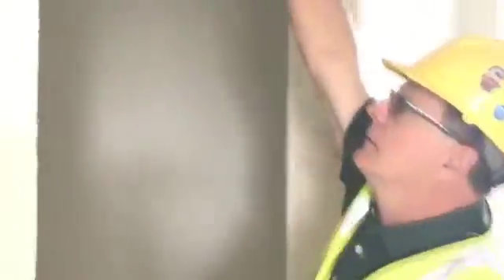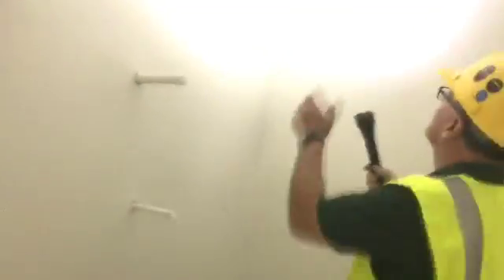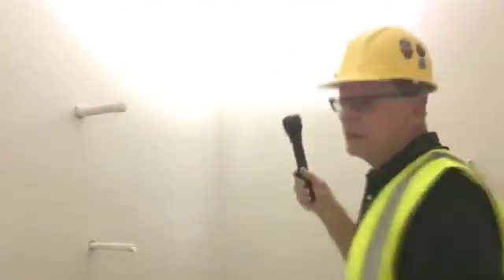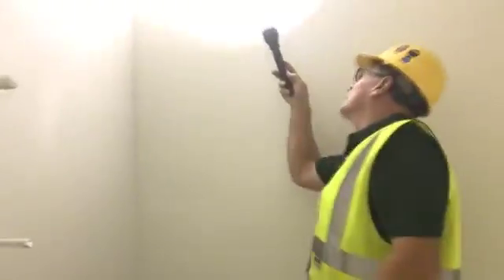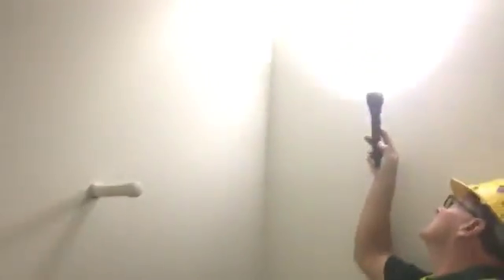So, we can take a look in the mechanical room. We're using a central return. This is all hard pan to get into here, or hard line. We have our plenum drop. This is the supply drop to the air handler, which will be in here. And we have to do a duct leakage test with this in place. Our big areas of concern are always these tight spaces between the drywall and this plenum drop.